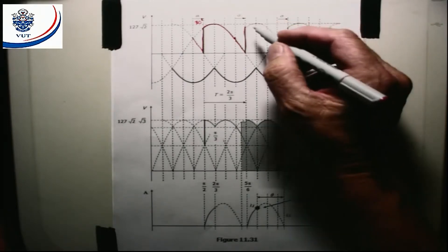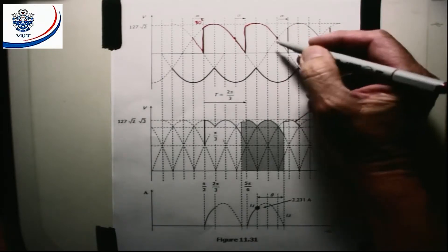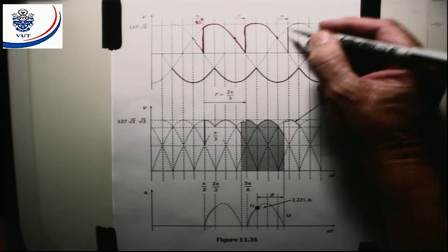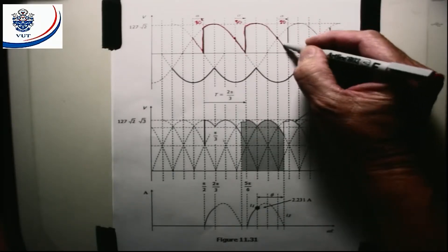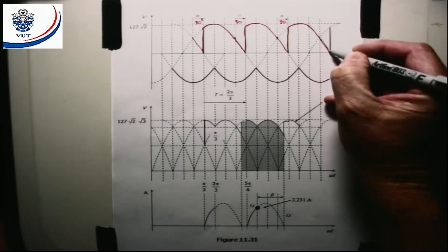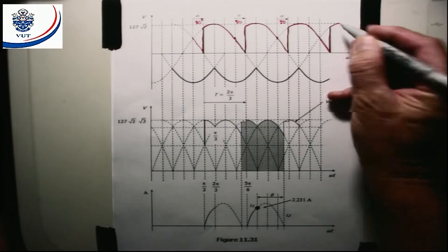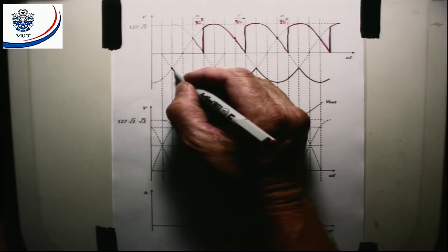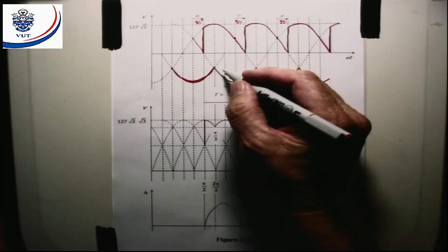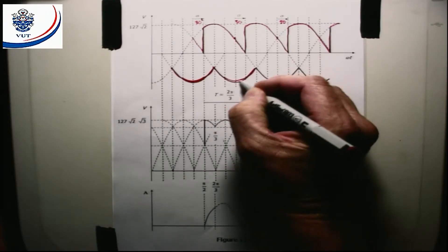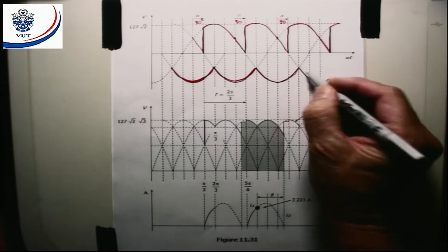Then we go to that phase. When we reach this point, the next diode would have switched on, but now we have a thyristor, so we will delay with another 30 degrees as indicated here. There we have the voltage appearing on the positive side on the motor. On the negative side, we've got three diodes. So if we reach this point, this diode will switch on and that phase will be supplied to the bottom part of the motor. When we get to that point, the next diode is forward biased and we will be following this line here, and the same there.